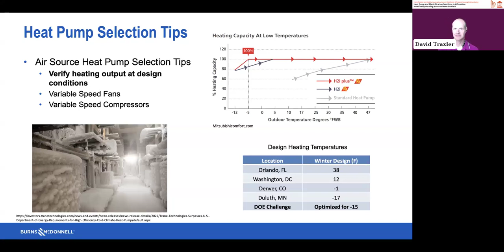One other thing I want to mention here is in some cases, your loads can be extremely imbalanced, like we saw before, where you have a very high heating versus cooling load. One thing that's important also is that the equipment be able to meet both of those comfortably. And that's going to require typically variable speed fans in your units and variable speed compressors. Almost all high capacity, high heating heat pumps have these, but it's something to be aware of. Next slide.